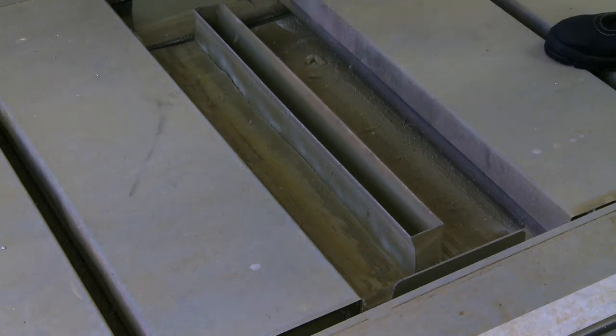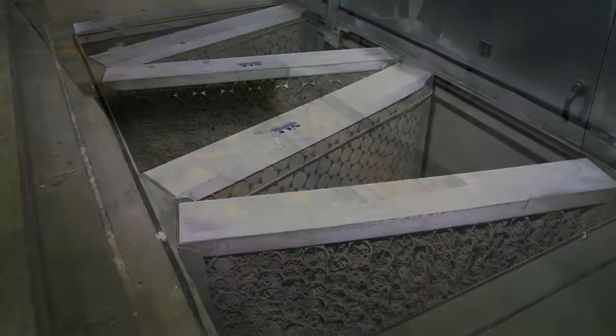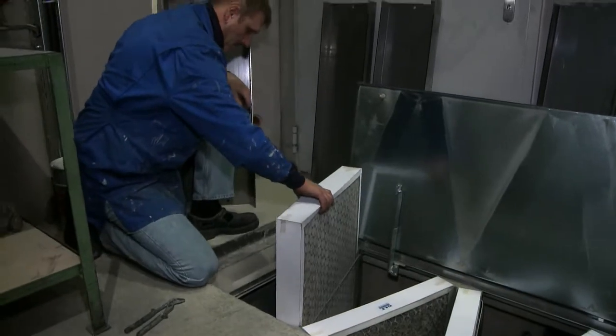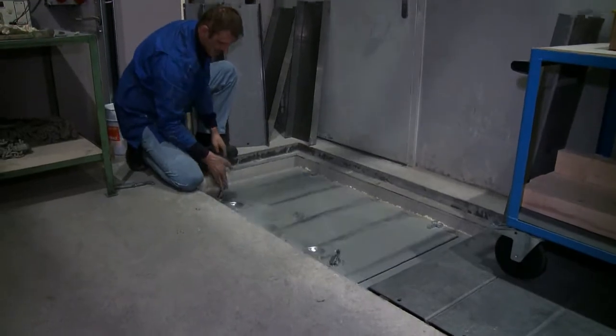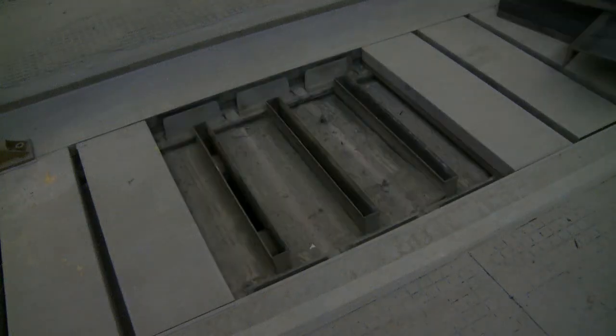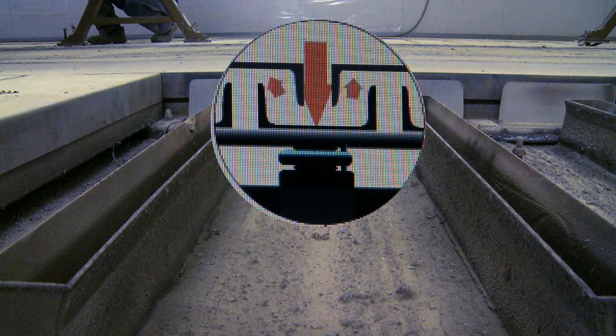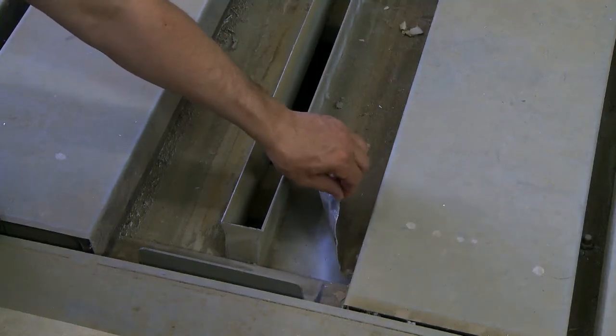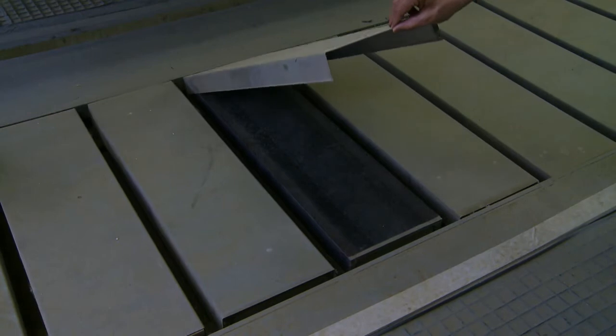The use of the impact separators also achieves significant savings by reducing maintenance costs for the filter mats by 80%. The replacement intervals for saturated filter mats are significantly longer, as only the smallest and lightest of the entrained particles must still be captured by the downstream filter mats. The route taken by the overspray airstream allows the entrained paint particles to precipitate out in a vortex-like zone of turbulence. The dried paint collects on an easy-to-dispose-of foil, and because the surfaces of the impact separators also collect overspray, they are equipped with an easy-to-exchange protective metal plate.